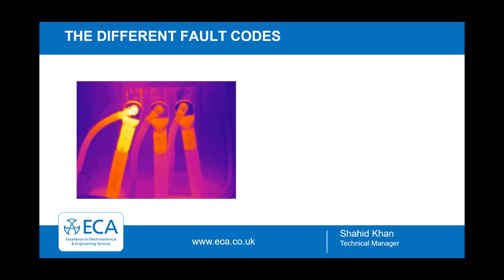Ah, a bit of overloading on one of the phases. So not all faults are visible and may require a degree of non-invasive testing via a thermal imaging camera. C2, potentially dangerous, risk of overheating and fire as phase 1 is burning hotter than the others. That's what I'd give it.